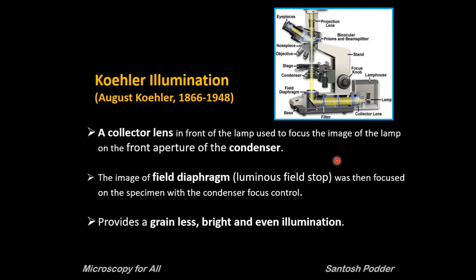The illumination technique we discussed today was first described by August Köhler from Carl Zeiss Corporation in the late 19th century as a method of providing optimum specimen illumination, and it is still widely employed for modern microscopes even over 100 years later. In Köhler illumination briefly: a collector lens in front of the lamp focuses the image of the lamp on the front aperture of the condenser, and the image of the field diaphragm is focused on the specimen with the condenser focus control. This technique is now adopted by all manufacturers of modern laboratory microscopes because it provides grainless, bright, and even illumination, allowing the user to realize the microscope's full potential.